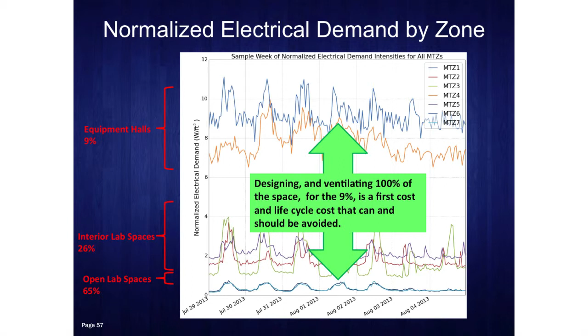And what we found out, sorry, it's hard to read, I'll explain it for you, is that those equipment corridors at the very end actually do almost reach 10 watts per square foot. And that's 9% of your space. 9% of your space was that high density equipment. Interior spaces, 26% was that support space where the biological safety cabinets were shown. A lot of times they also have microscopy rooms in there, those kinds of things. 65% of the space is open lab bay, those big open labs where I drew all those red arrows showing you how many things were plugged in.